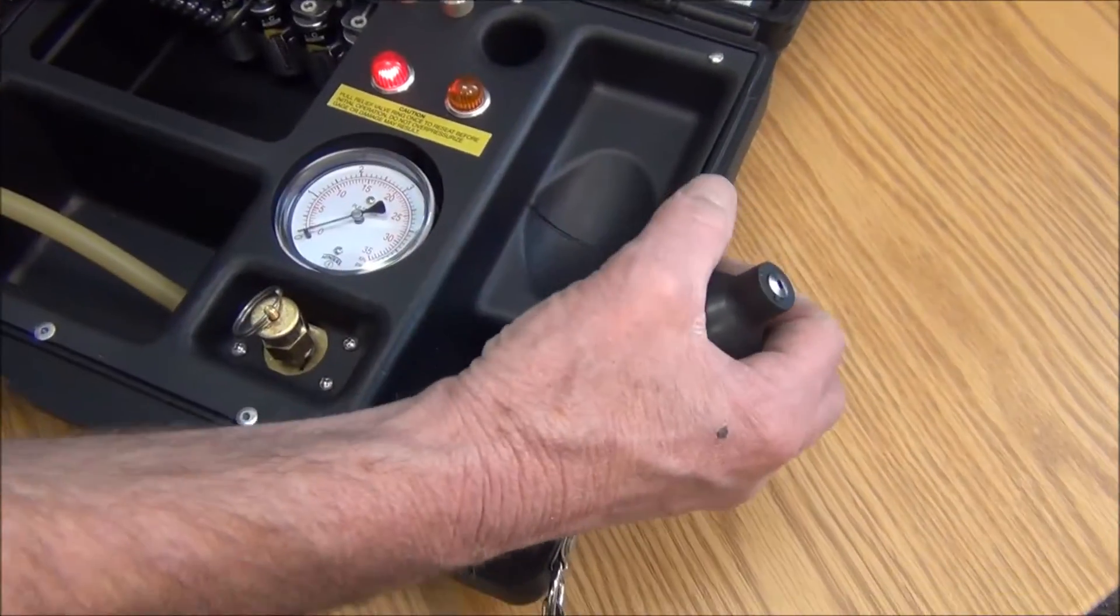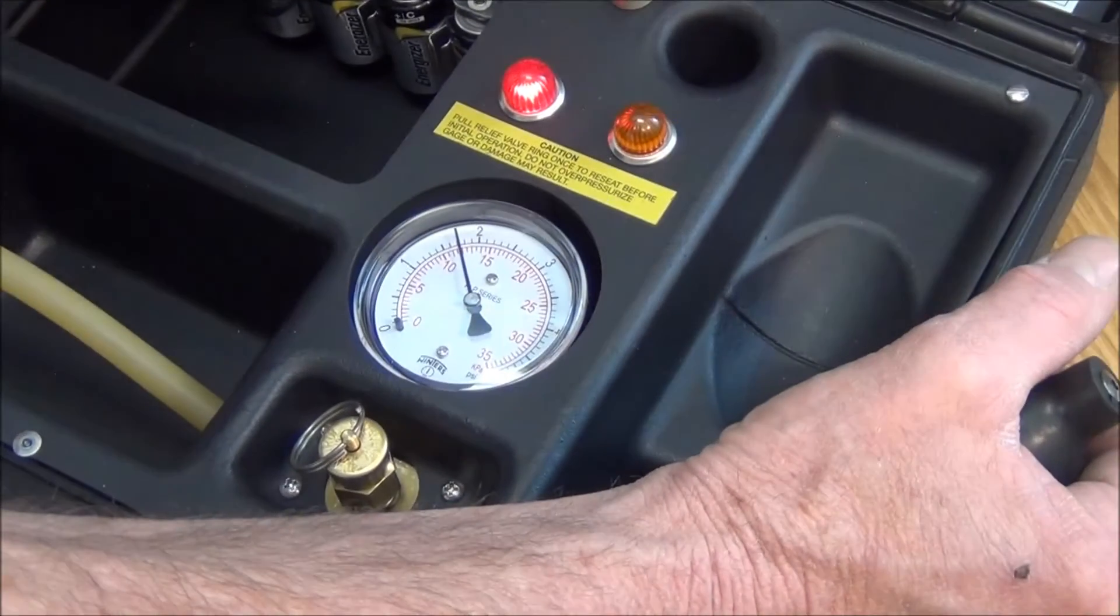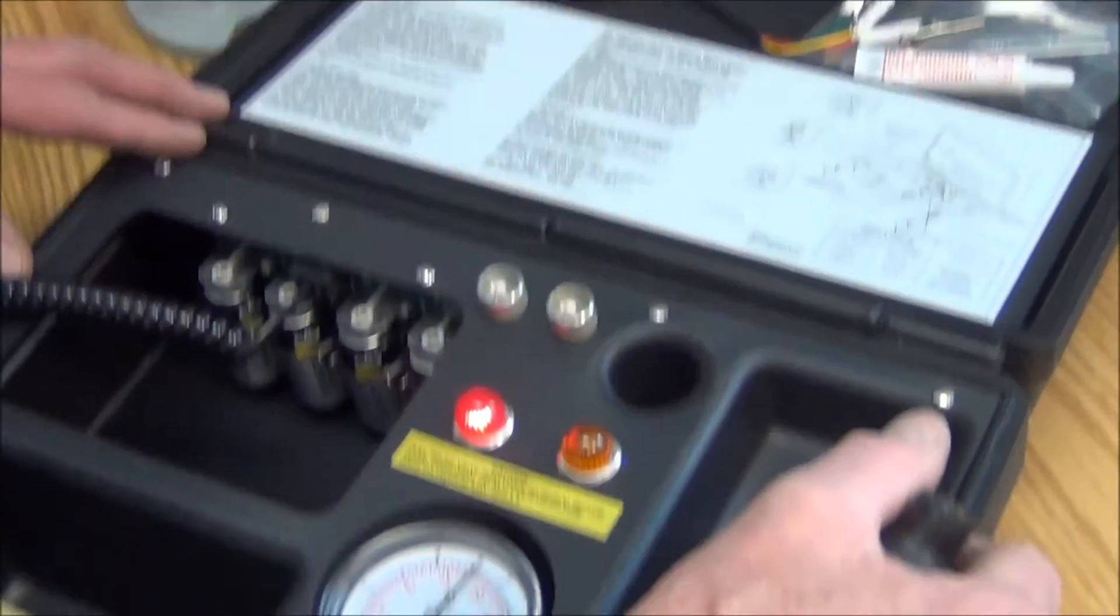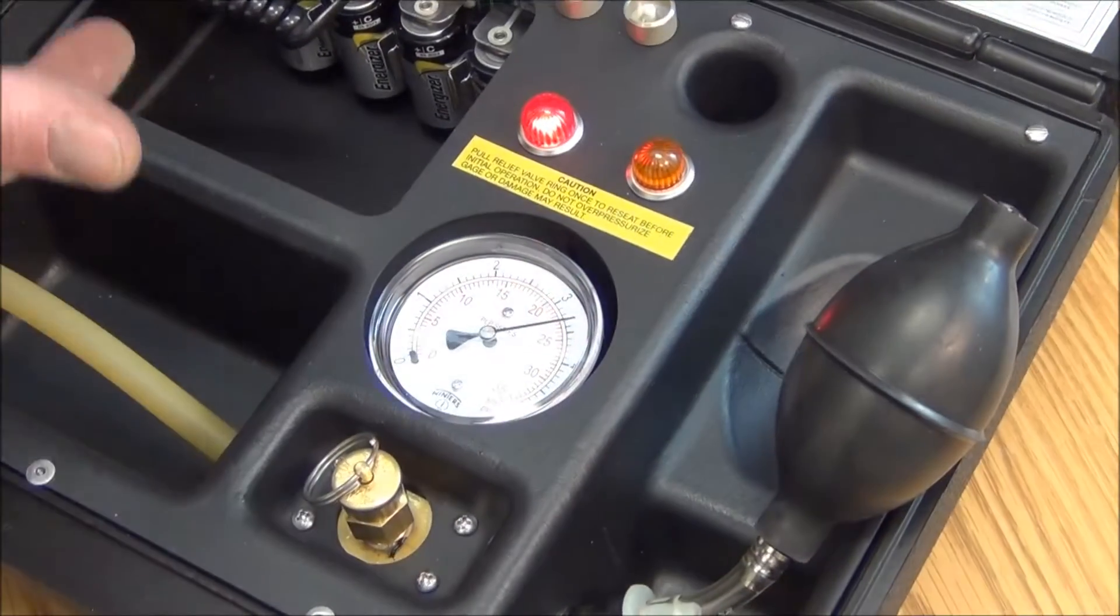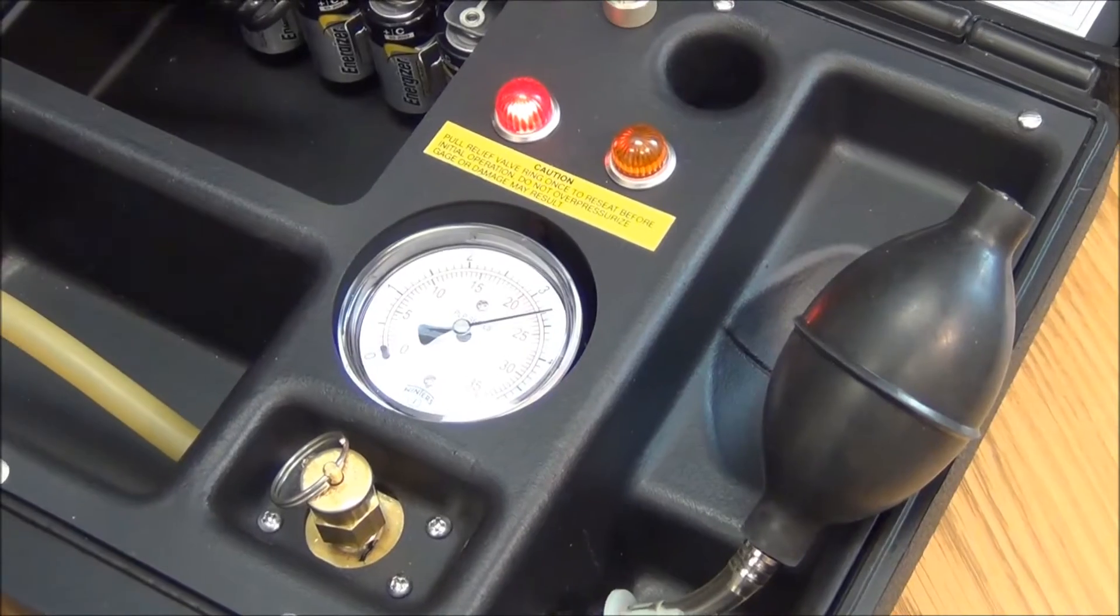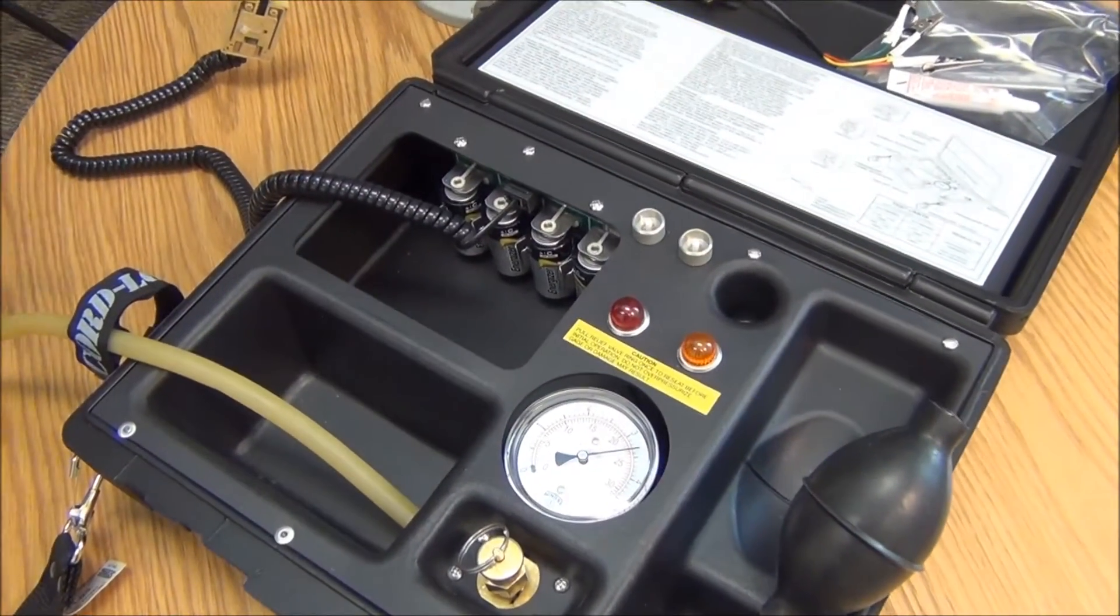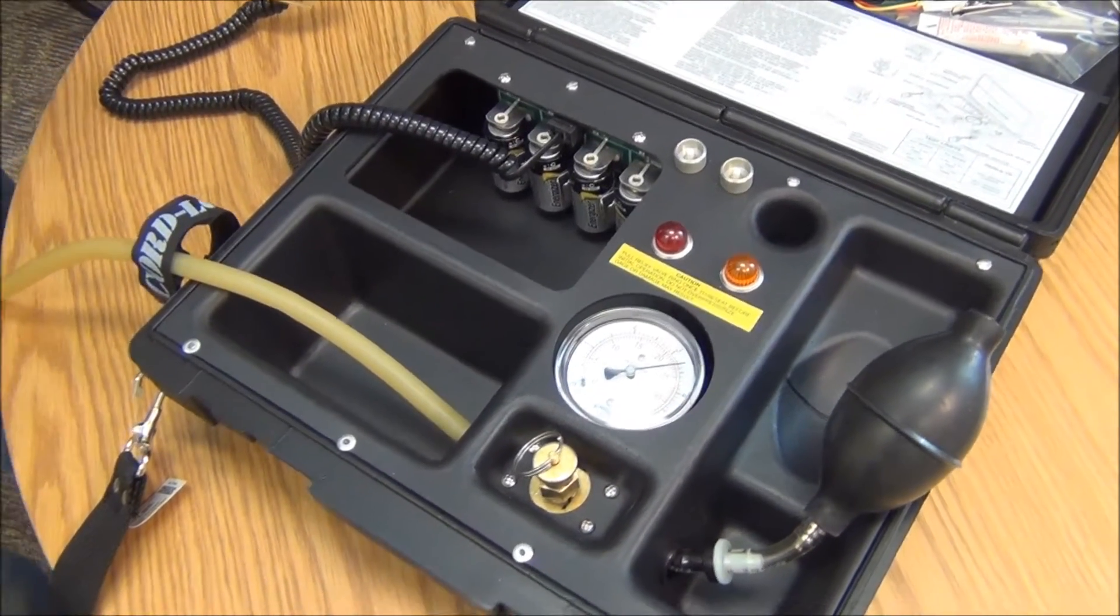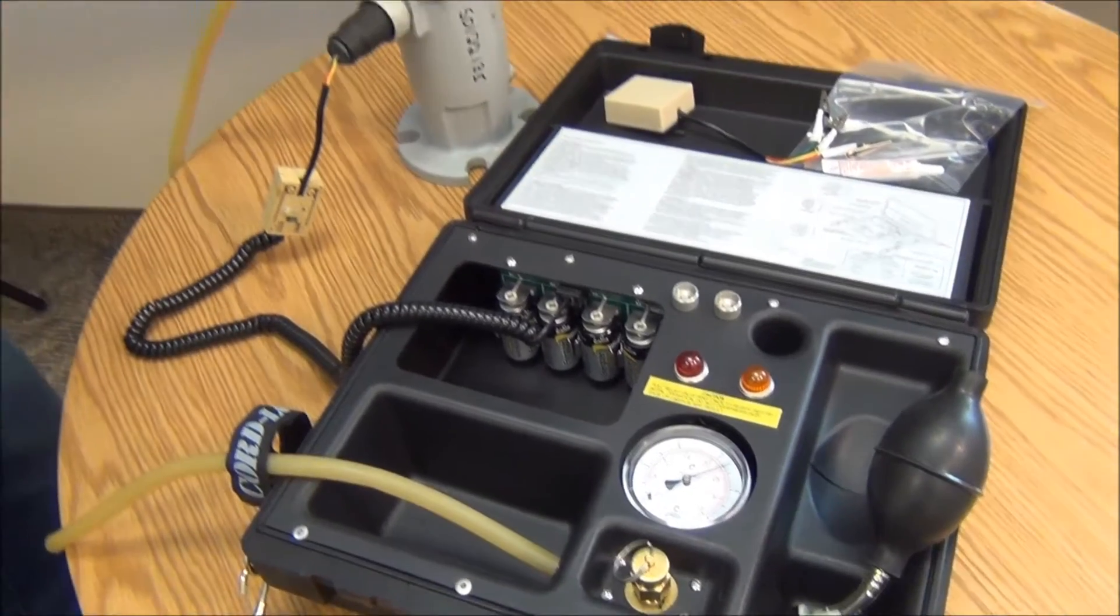The next step is to take this squeeze bulb. There's a chart on our instruction sheet to tell you what pressure to run this up to. For a 900, it's between 3.25 and 3.5 PSI, which I've reached. Once you reach that, you push the right button and the timer comes on for about 60 seconds. You have to wait 60 seconds to let the unit stabilize.